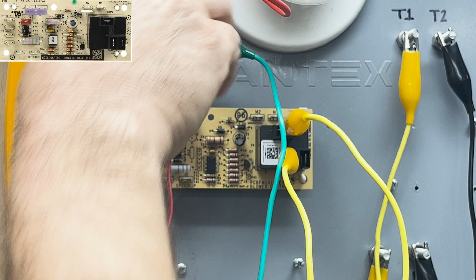Right above common, that R - this is the output that I would wire my thermostat to. But before I go to my thermostat, maybe I want to go to a float switch. After my float switch, then energize my thermostat. Then after my thermostat, you'd get a G call, and that G call would come down here. So let's say we went through the float switch, out of the float switch, into the thermostat, and then energizing G through the thermostat base plate comes back as my G call. This is going to be where I represent my G call.